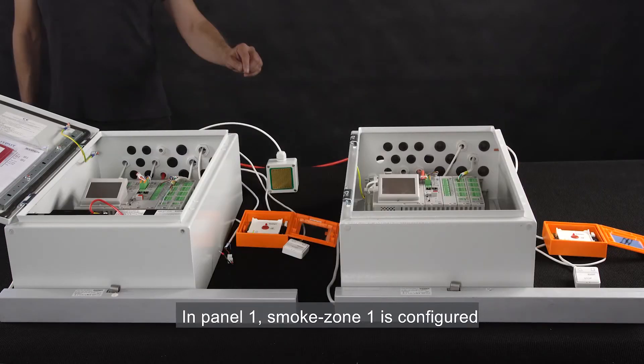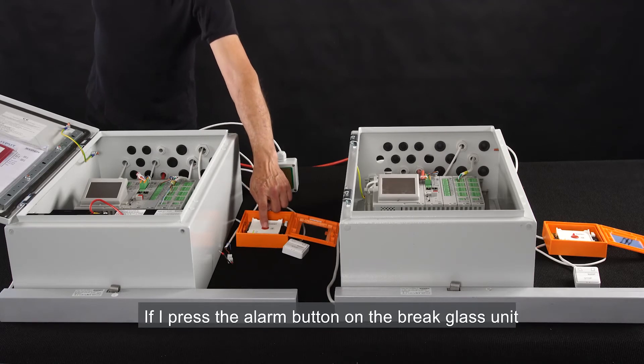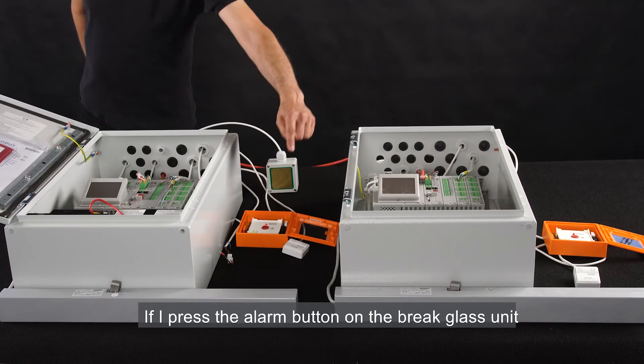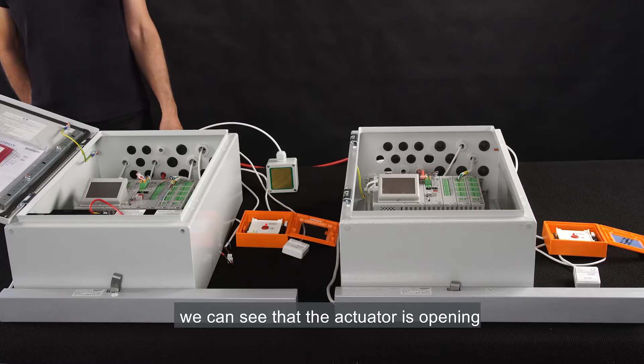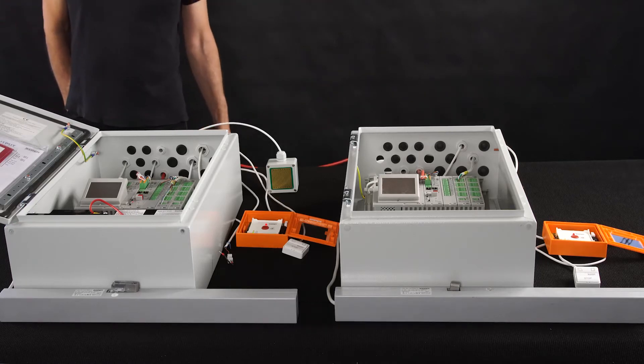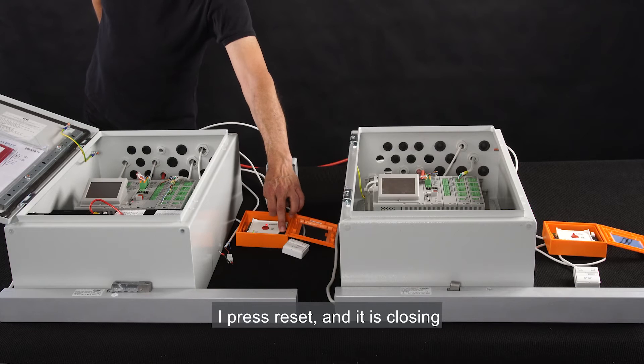In panel 1, Smoke Zone 1 is configured. If I press the alarm button on the break glass unit, we can see that the actuator is opening. I press reset and it closes.